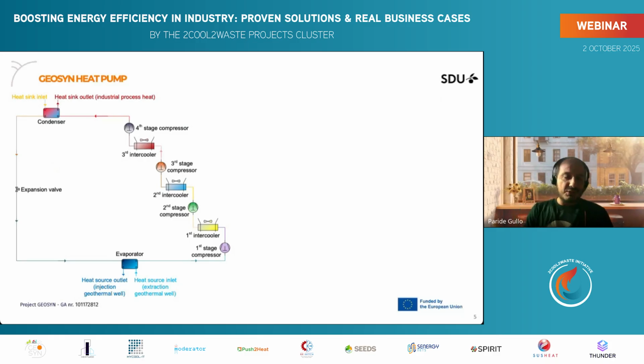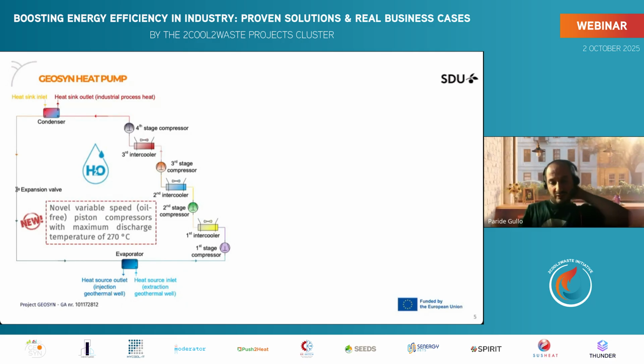In this slide you see a simplified schematic of the heat pump we are developing in our project. You can see we have 4 stages of compression, with intercoolers in between. The idea is to connect the heat pump to a geothermal well in Italy, which will act as the heat source. On the heat sink side, the target is to generate heat up to 180, even up to 200 degrees Celsius. The refrigerant will be water, and the compressors are novel, variable-speed, oil-free piston compressors, with a maximum discharge temperature of around 270 degrees Celsius.